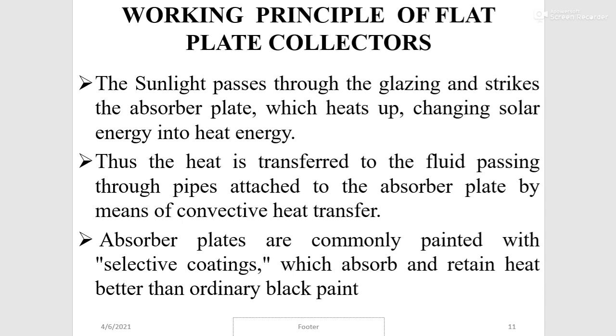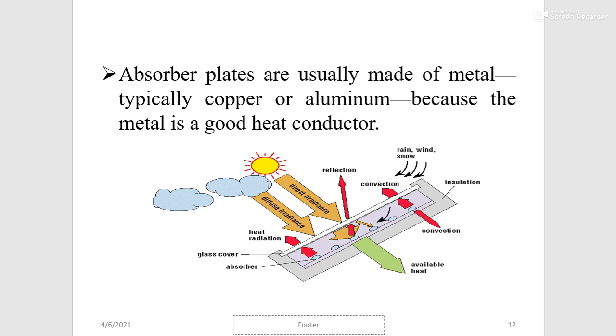The working principle of flat plate collectors: sunlight passes through the glazing and strikes the absorber plate, which heats up, converting solar energy into heat energy. The heat is transferred to the fluid passing through pipes attached to the absorber plate by means of convective heat transfer. Absorber plates are commonly painted with selective coatings which absorb and retain heat better than ordinary black paint. Absorber plates are usually made of metal — typically copper or aluminium — because metal is a good conductor of heat.